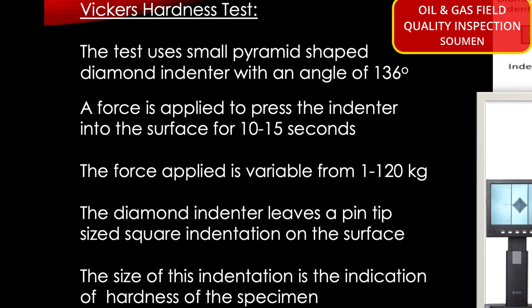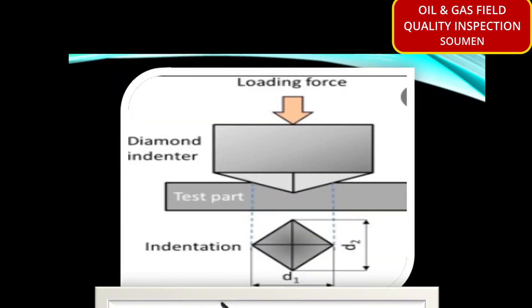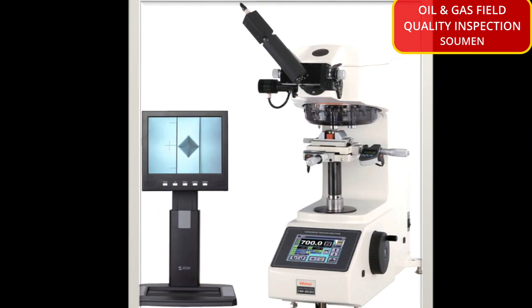The Vickers hardness test uses a small pyramid-shaped diamond indenter with an angle of 136 degrees. A force is applied to press the indenter into the surface for 10 to 15 seconds. The force applied is variable from 1 to 120 kilograms. The diamond indenter leaves a pin-tip size square indentation on the surface, and the size of that indentation is the indication of the hardness of the specimen.